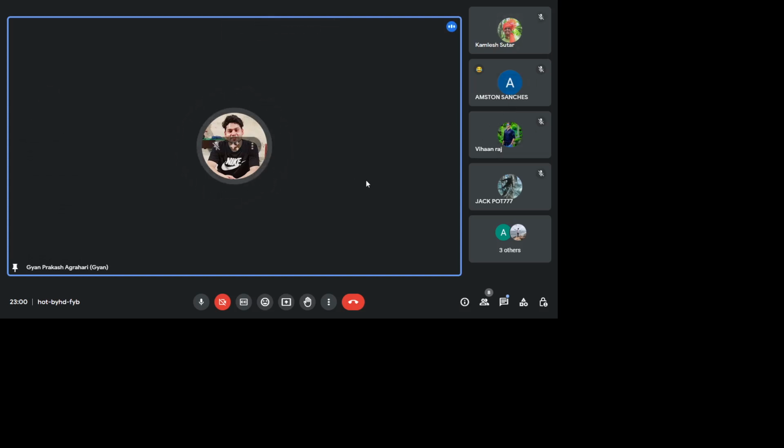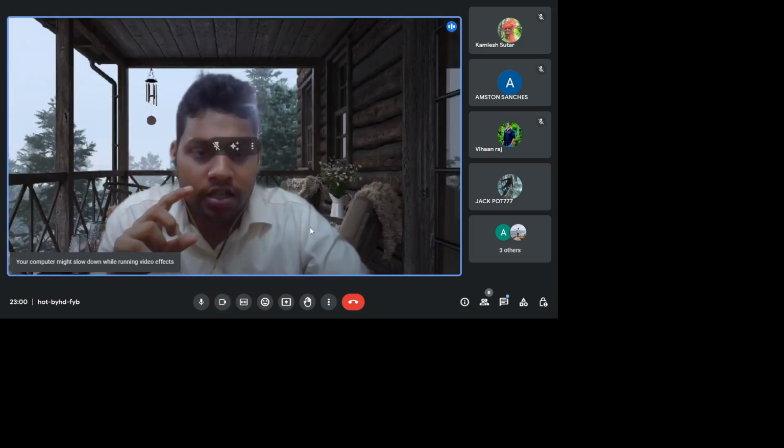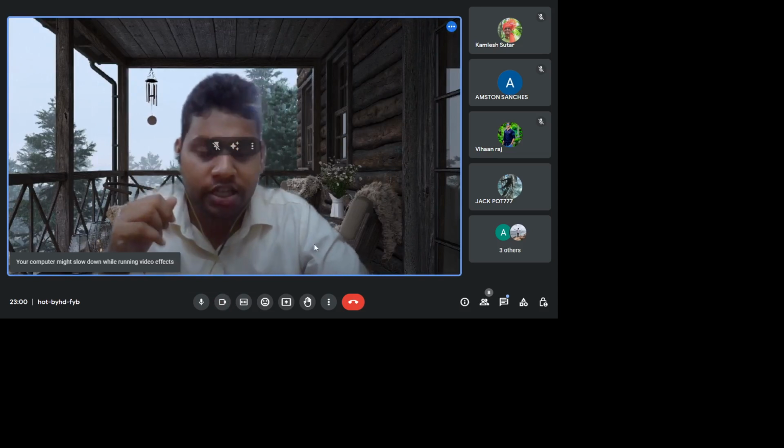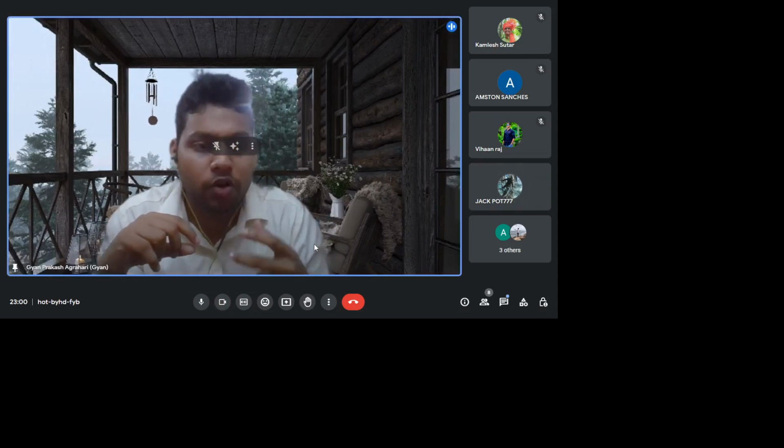So fusible plug, guys, remember, it is used to prevent damage to the boiler from overheating. It is made up of soft metal alloy that melts when the temperature of the water reaches a dangerous level, allowing steam to escape. It is a kind of threaded cylinder structure in which the middle part is made of soft alloy.